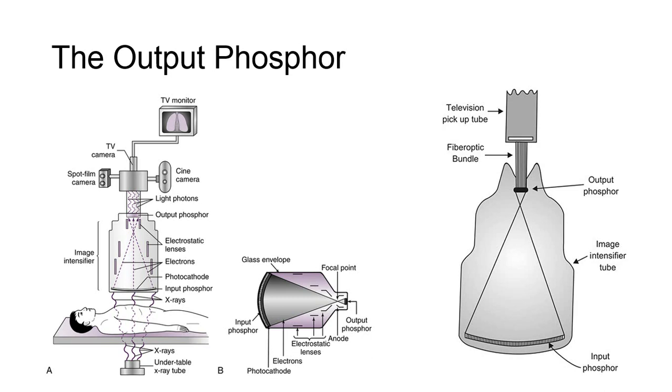It should be noted that the image received at the output phosphor is upside down compared to the image received at the input phosphor. This is because of the focal point created at the anode within the image intensifier.